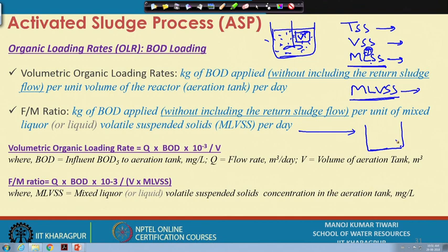activated sludge process is primarily bacteria. Some initial seed is provided anyway, and then there is a growth of microorganisms, and these microorganisms are also suspended solids because they cannot dissolve in the water. They remain in suspension, and that is why we call it a suspended growth system. Since they remain in suspension, these microorganisms are part of the solid matrix of the water, and so when we monitor the solids in an activated sludge mixed liquor system, what we get predominantly is the microbial biomass.